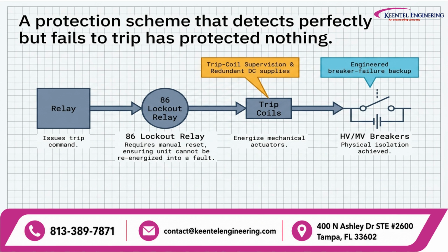Every link in this chain matters. A relay can make the correct decision, but if the trip circuit is open, a control fuse has failed, a lockout relay is malfunctioning, or a breaker mechanism does not operate, the electrical fault remains connected.